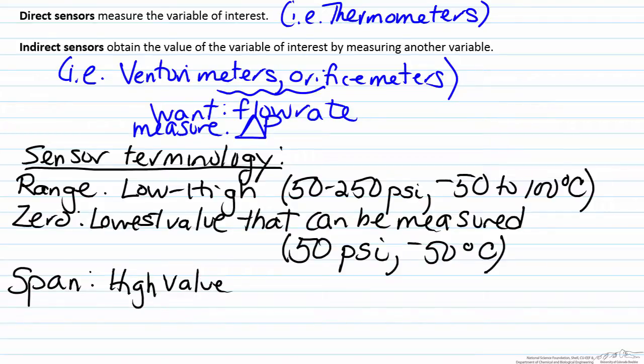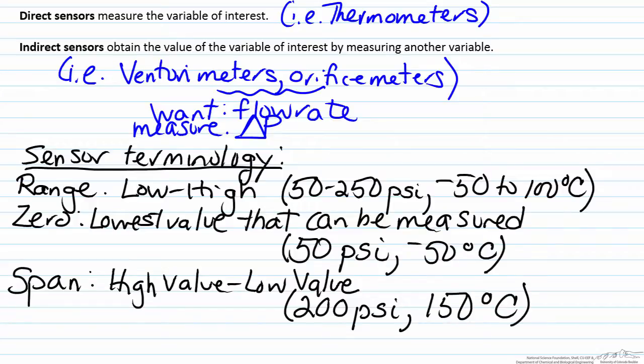The span represents the magnitude of the high value minus the low value. So in the case of what we have here, going from 50 to 250 psi, the span would be 200 psi, and for the temperature sensor going from negative 50 to 100 degrees Celsius, this would be a span of 150 degrees Celsius.